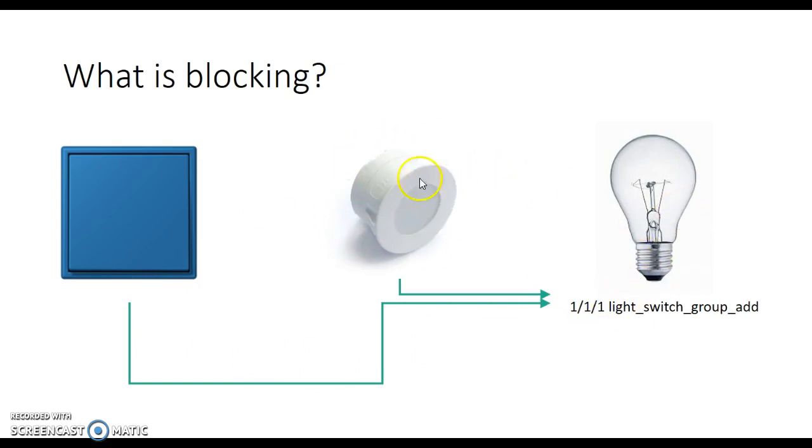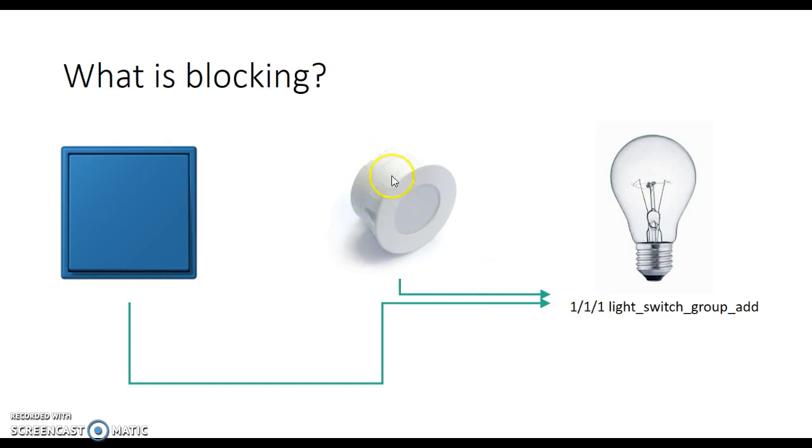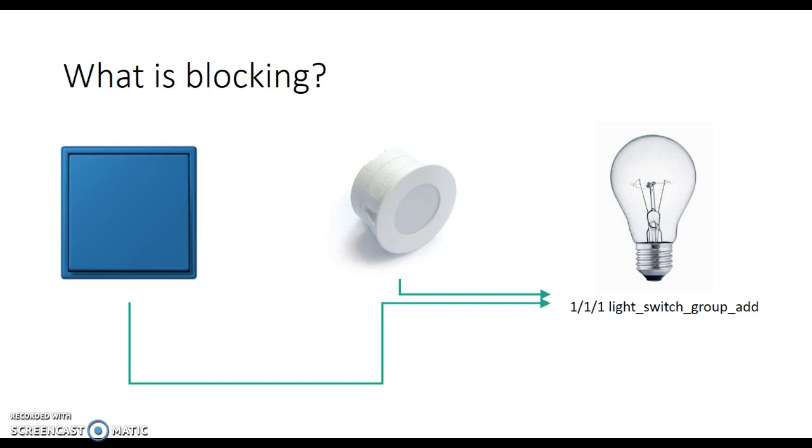Similarly, if movement is sensed in the room it will send a 1 to this and then at the end of a sort of predefined time which you can program into this object, into this movement sensor, maybe 2 minutes or so for example, it will automatically send an off switch, an on-off message to this group address.